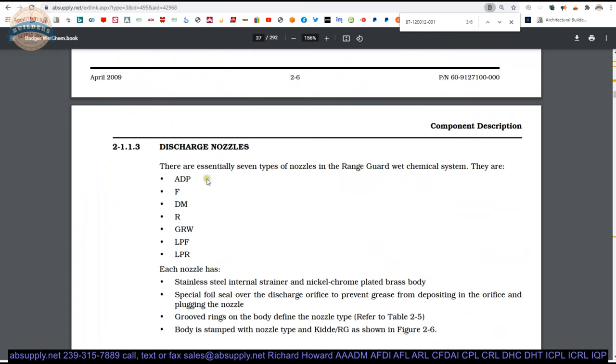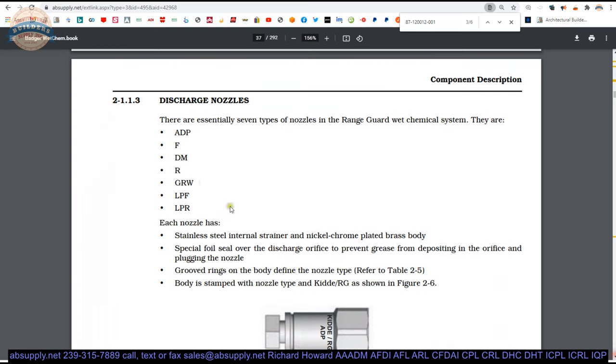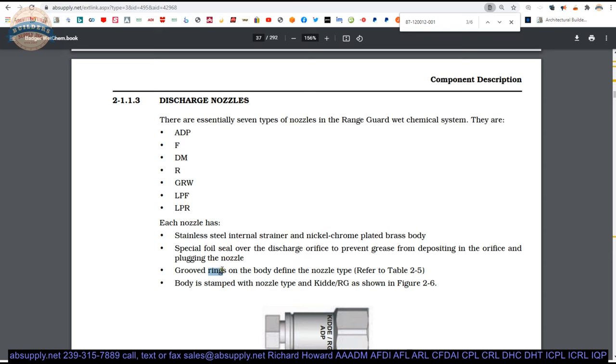Discharge nozzles. There are seven types of nozzles that are listed here. Each nozzle is a stainless steel internal strainer, nickel chrome plated brass body, special foil seal over the discharge orifice to prevent grease from depositing in the orifice and plugging the nozzle.